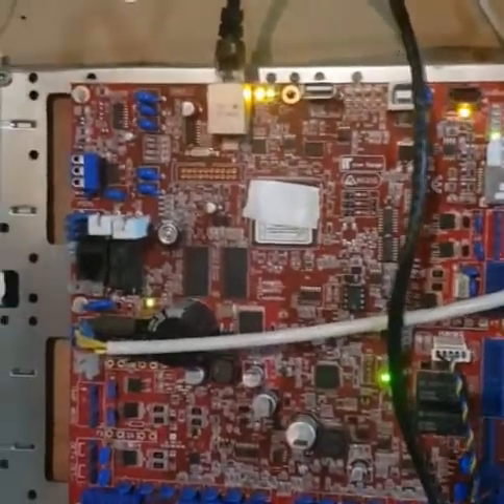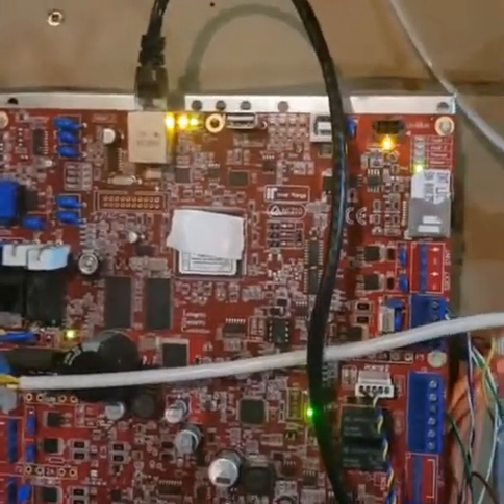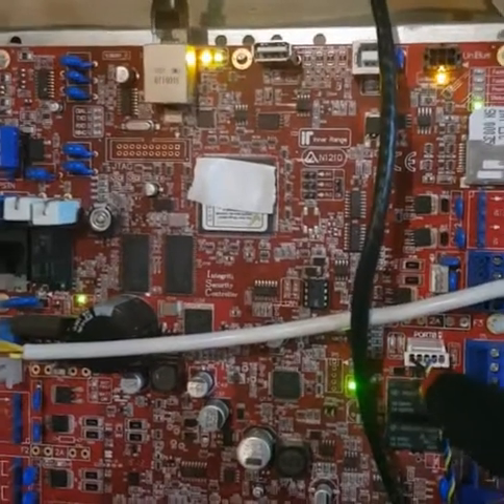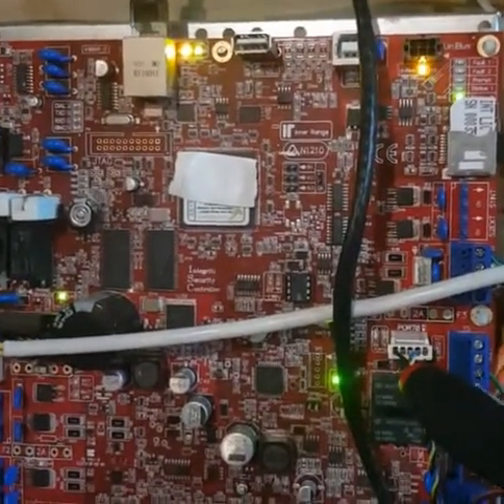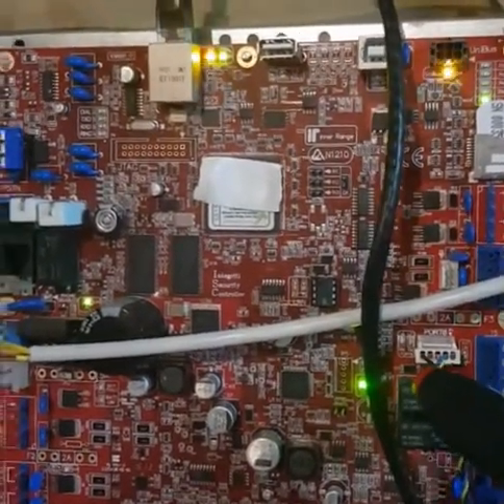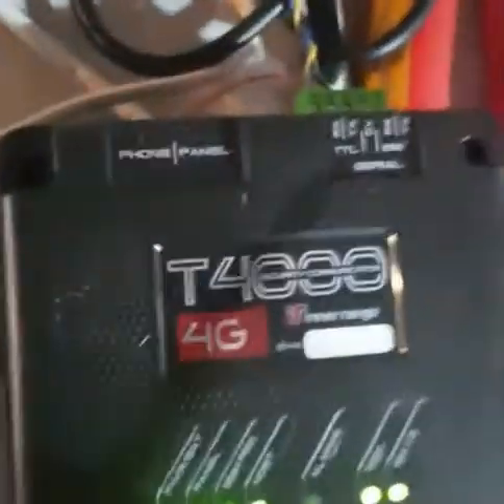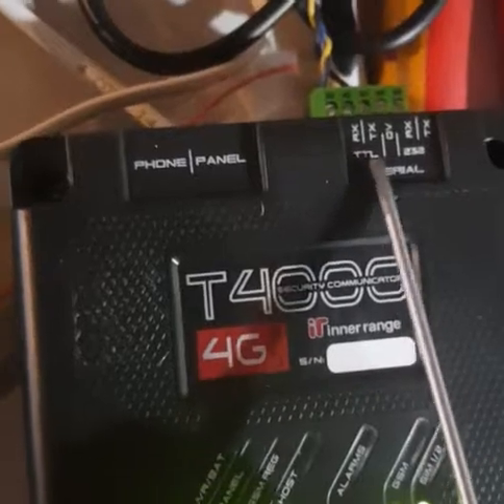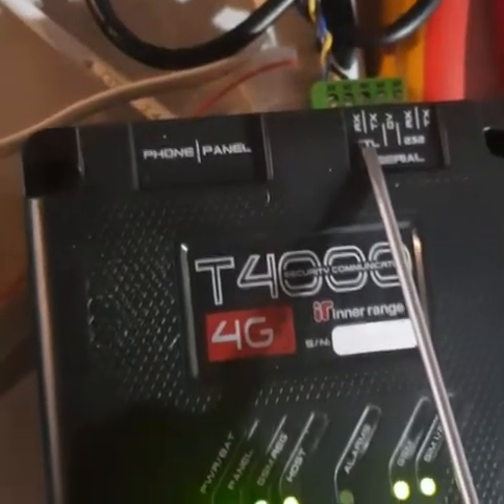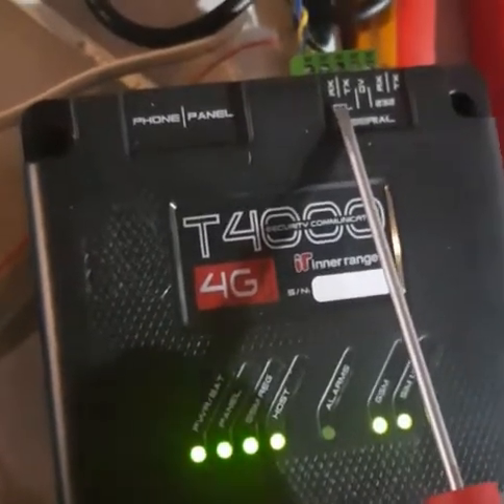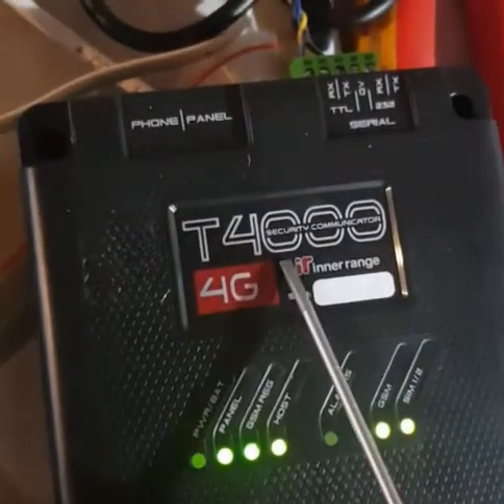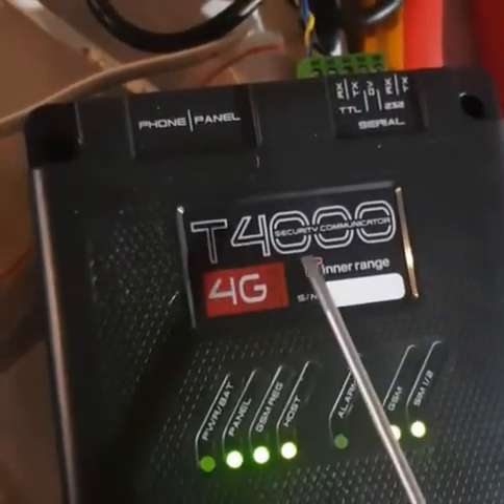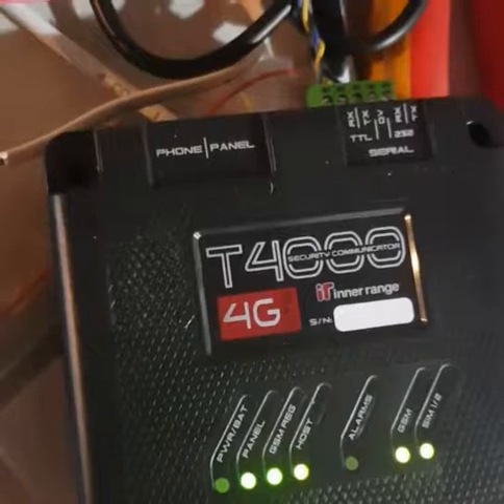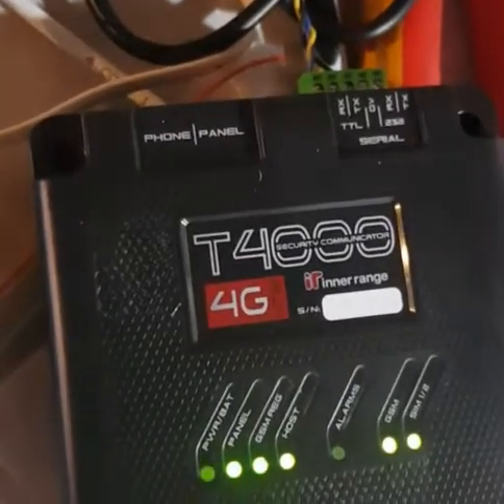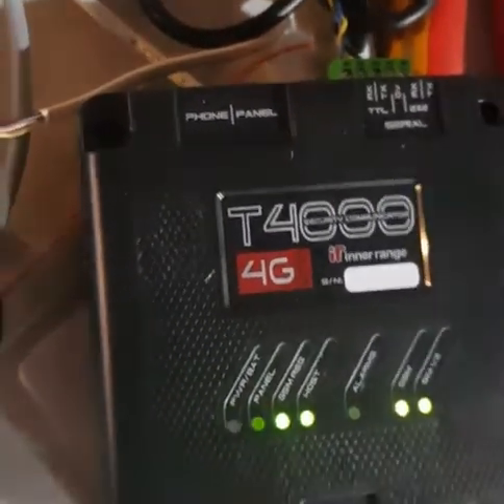This is my Integriti alarm panel setup. It is connected to the T4000 via the serial interface cable at the port 0 connection up here, and also connected on the T4000 to the TTL connection. If you're talking to the monitoring via IR fast format from the T4000, you need to make sure your monitoring connection has been set up to IR fast communication mode.